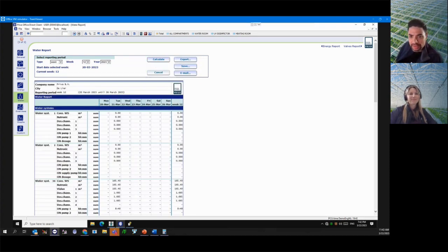I saw another question here. The dosing channel, does the dosing ratio dictate how long the dosing valves from A to B stay open? No, there are dealer settings where we put in a number. So there's a cycle time, so it pulses, and then there's a cycle time where it looks at the EC measurement, and then it pulses again if it needs to, and there's a maximum pulse length. So you might see that your pulses start to increase and decrease, right? Initially, I think we set the minimum pulse for the first pulse to like half a second or 0.4 seconds or something like that, but it might stretch out a little bit longer than that.